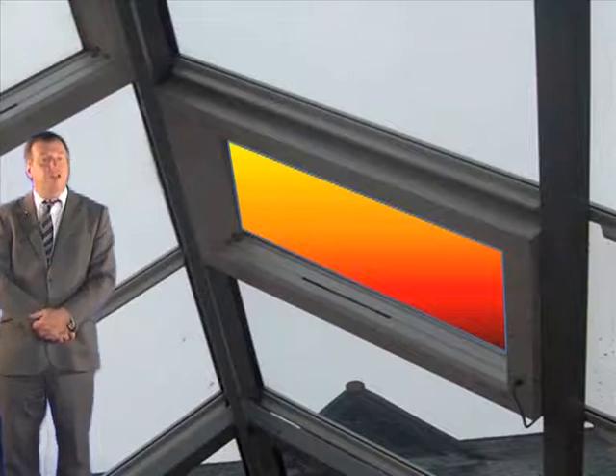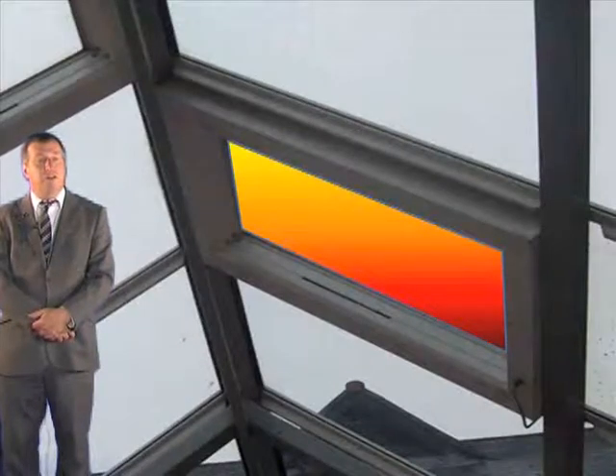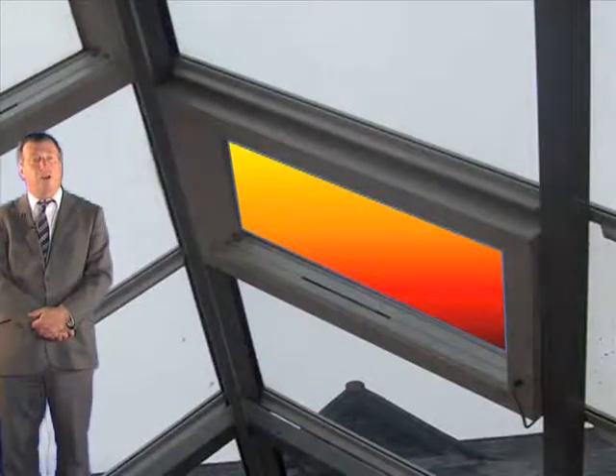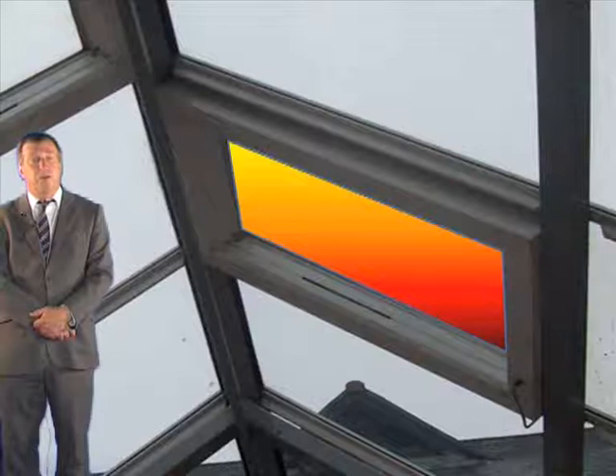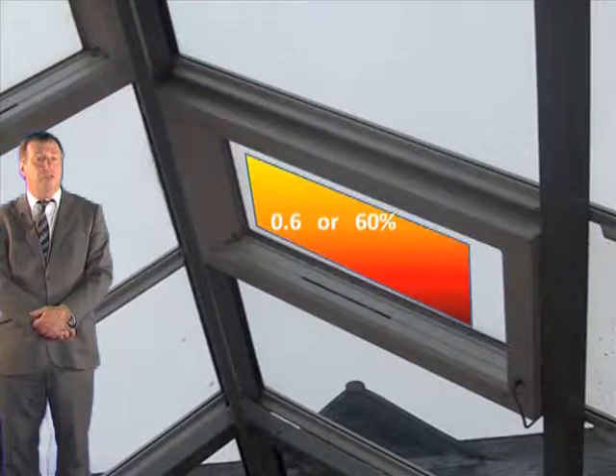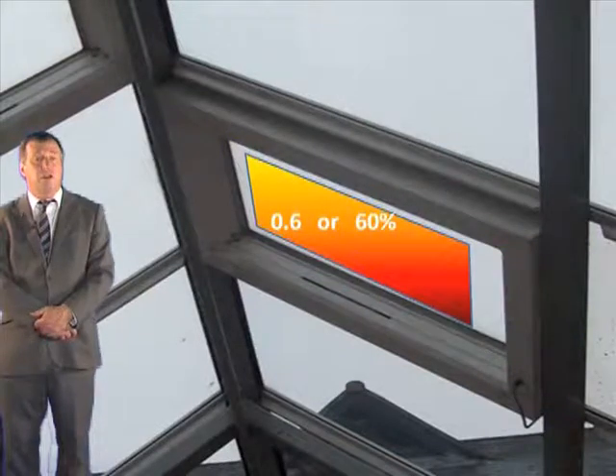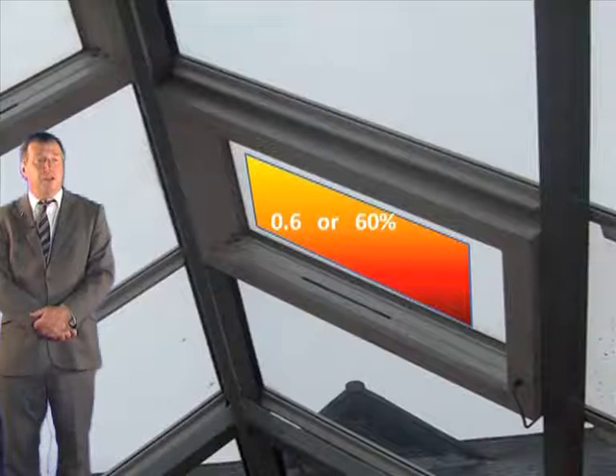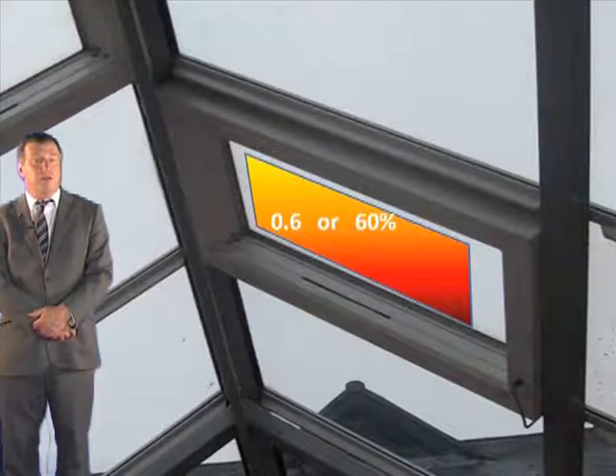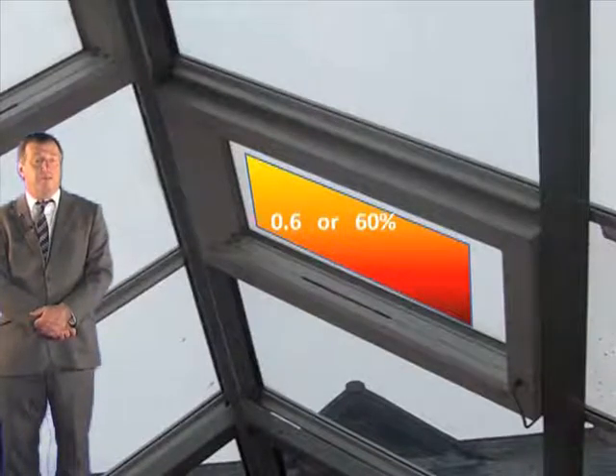Remember from the section on natural ventilation that vents are not 100% efficient, and we assume the default value of 0.6, or 60%, for the coefficient of inlet. This applies even if the vents being used are doorways.